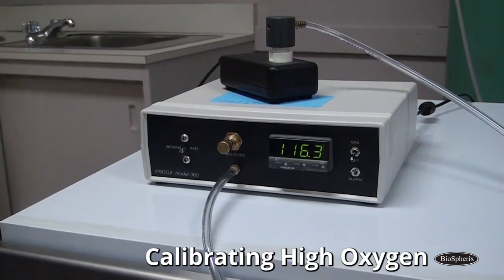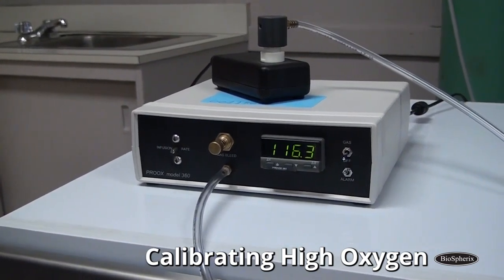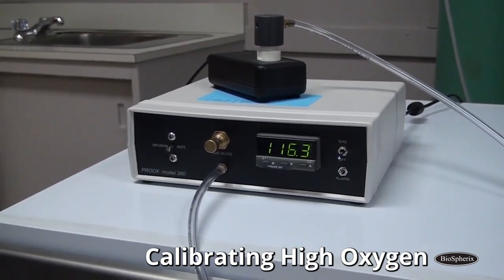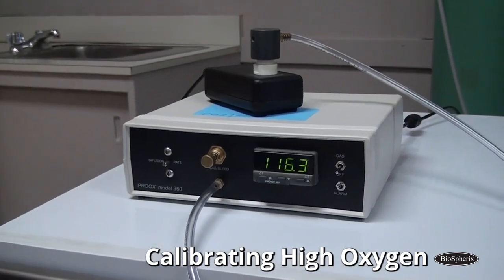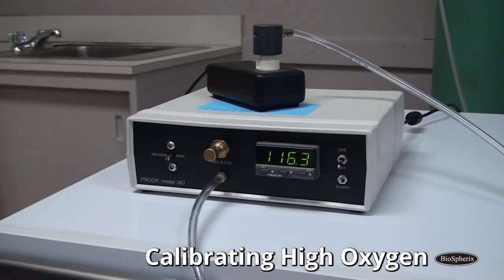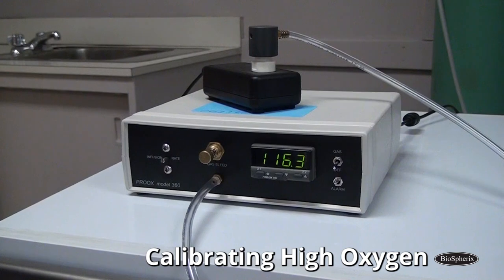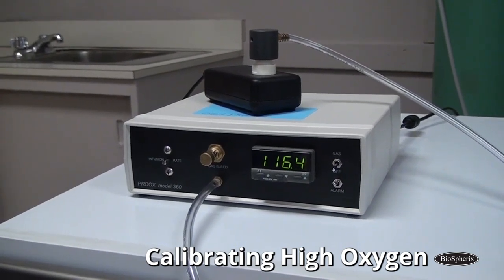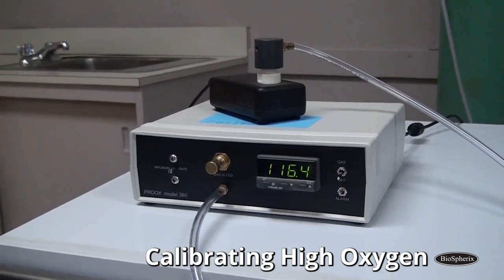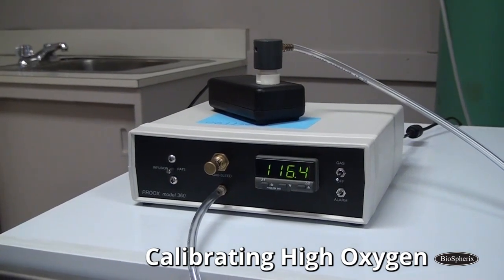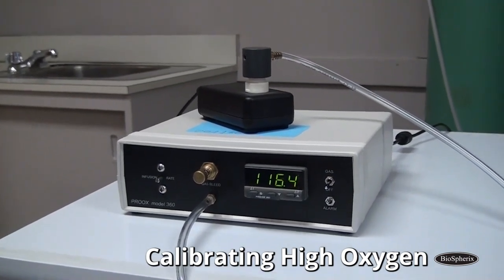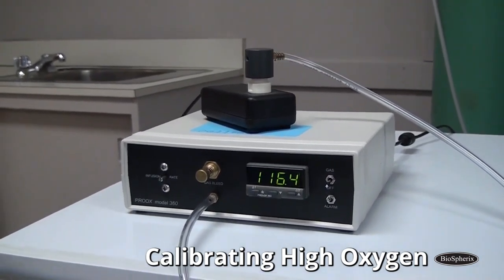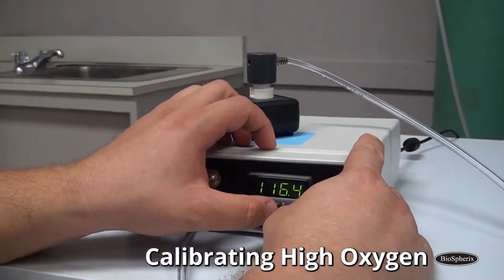Okay, we've let it sit for a couple minutes here. Again, you just want to let it sit till it pretty much stabilizes. It's pretty steady here. It's reading 116.3, so we're way above 100% here, which is really common when you do a new sensor, because your span number needs to come down. So we need to make an adjustment to the span.